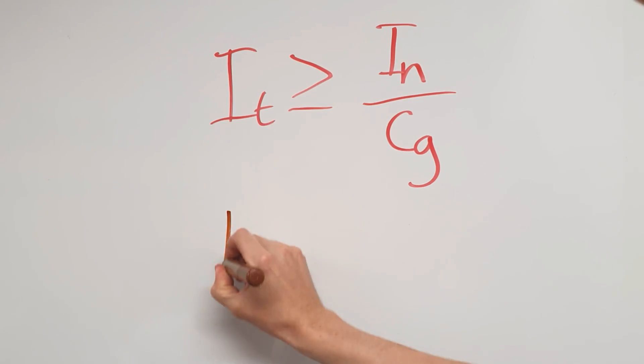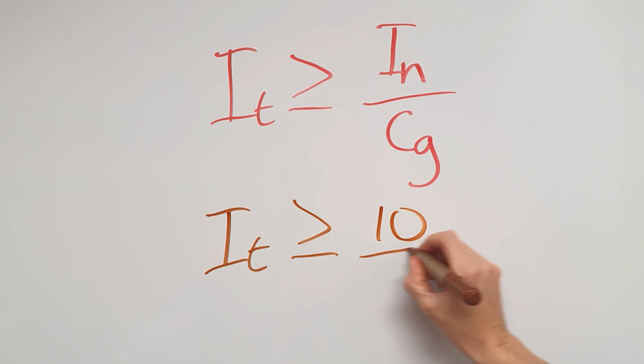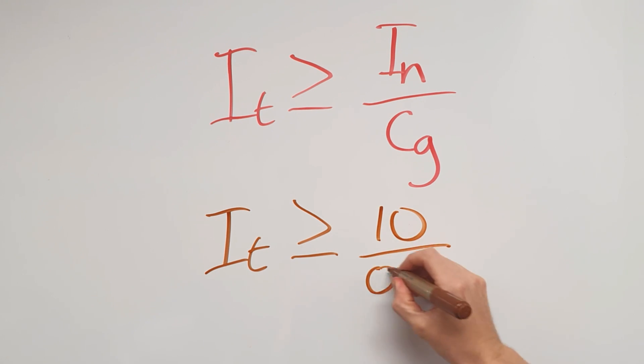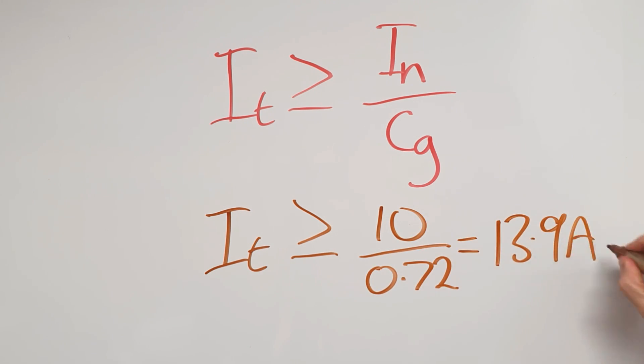There are a whole load of other rating factors that we can put under here to keep the grouping factor company, but we'll cover those in other videos. So if we're considering this lighting circuit protected by a 10 amp MCB, then the cable we install must be able to carry more than 10 divided by 0.72 — so 13.9 amps — and then we'd select the correct cable accordingly. But is that the end of the story?